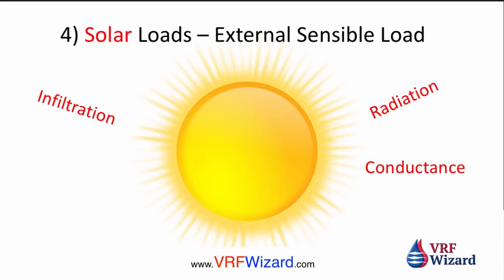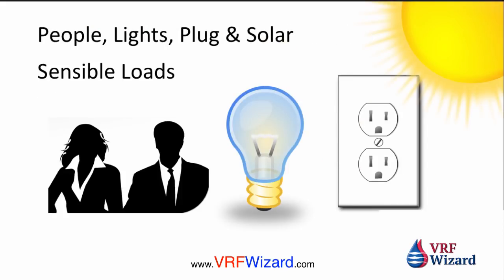The fourth contributor is the solar load — that external sensible load. We're only going to deal with sensible heat, which includes radiation and conductance. We also have infiltration, which brings in some sensible load, but it's a small amount — it leaks in through doors and window cracks. Newer buildings are tighter, so we're not going to cover infiltration. The four major loads are: people, lights, plug loads, and solar.